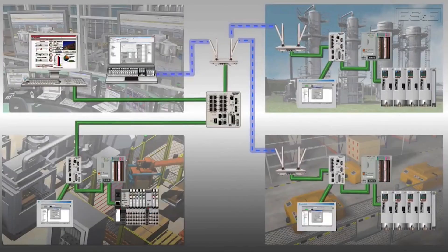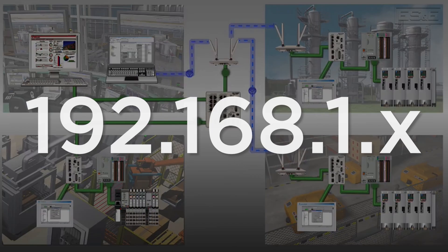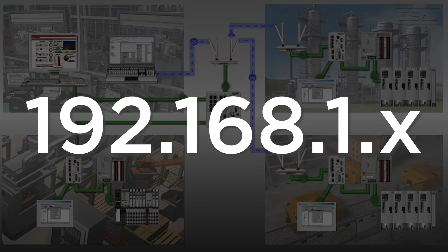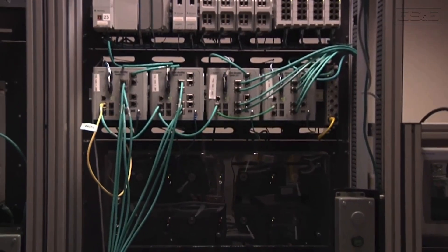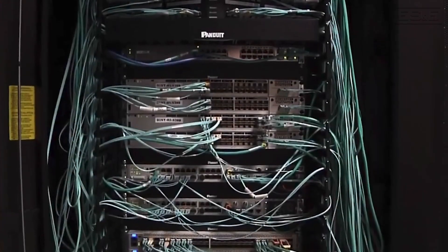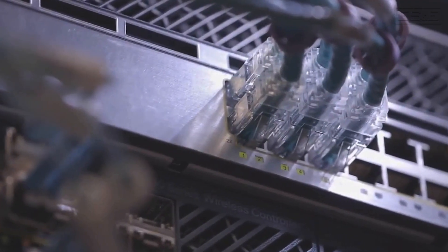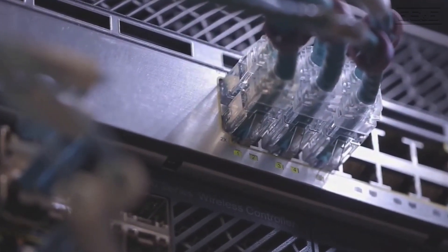I run into situations where there are a bunch of Ethernet devices spread across multiple production lines. They're huge networks and they all have that famous 192.168.1.x network. The biggest problem is that when they have a network issue it affects the entire line, multiple lines, so they don't know where to begin troubleshooting. Also it's almost impossible to add devices because they're out of IP addresses. They really need to think about breaking up their networks — it's called segmentation.